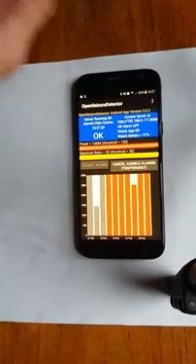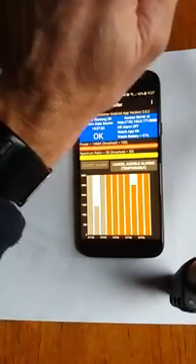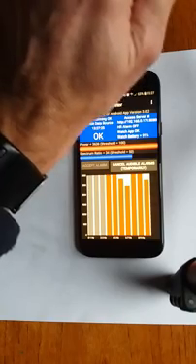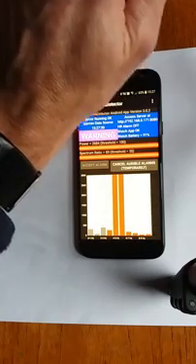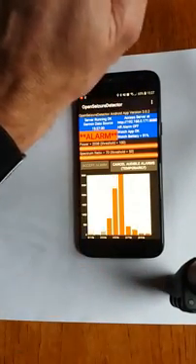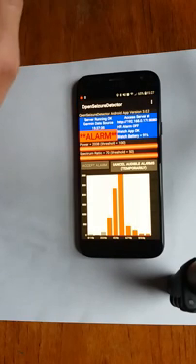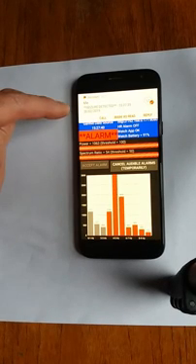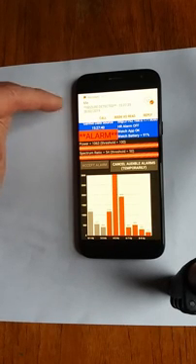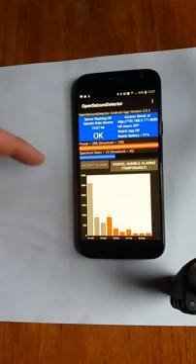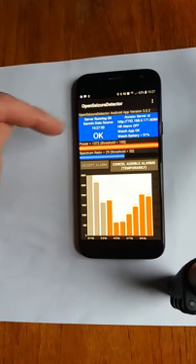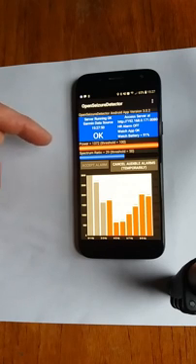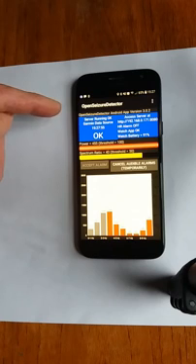And then we'll just give the classic sort of shaking that we're looking for as far as a tonic-clonic seizure is concerned, which is that sort of movement of the wrist, a few hertz movement. The system goes into warning first, and then it will go into alarm after a few seconds of that movement going on. So the first thing it does is it sends a text message that just says there's a seizure detected, and it sends that to the carer. For this demonstration, I've got the carer's SMS phone number set to be the same as this device. So we saw the alarm arriving there.